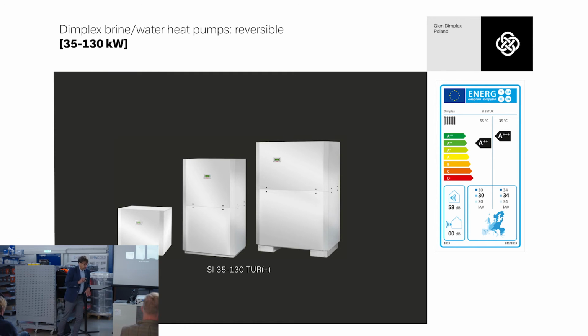Reversible brine to water heat pumps. Reversible means for heating and cooling. And the range is 35 up to 130. This machine can operate during the winter time for typical heating purposes, but during the summertime, it can convert via four-way valves on the refrigerant circuit and produce also cooling. In the case of brine to water heat pumps, the waste energy can be implemented into the ground with the regeneration of the ground. This is the advantage.